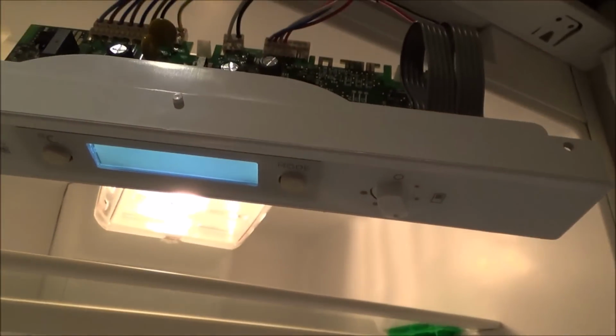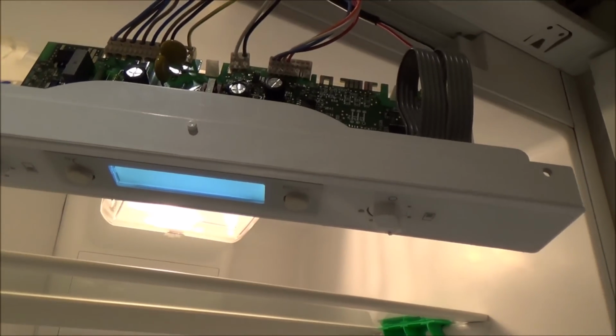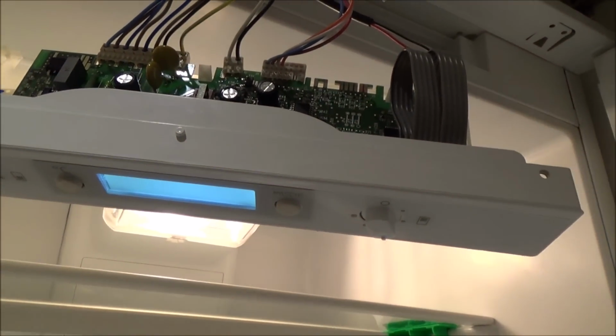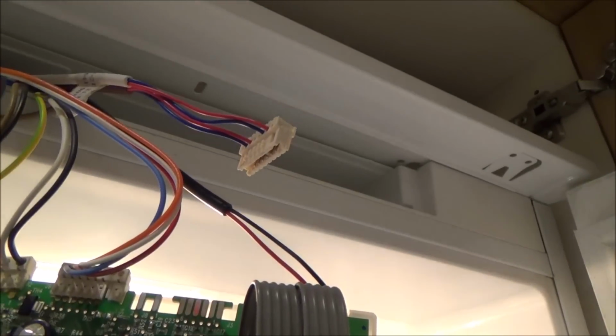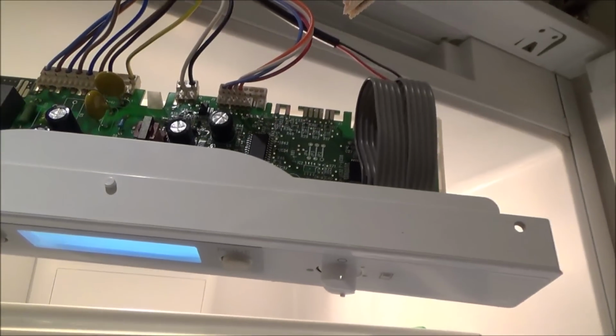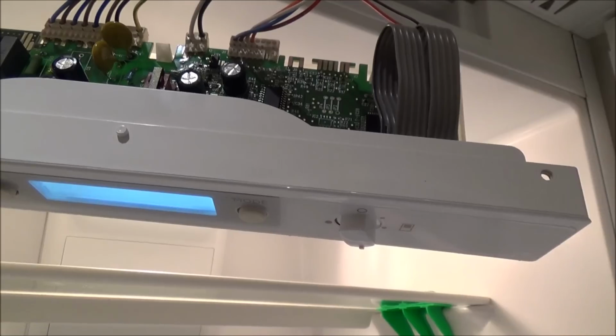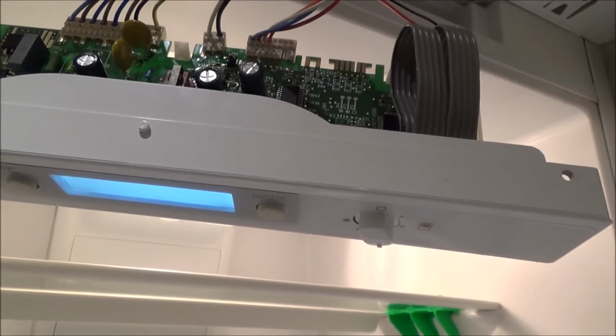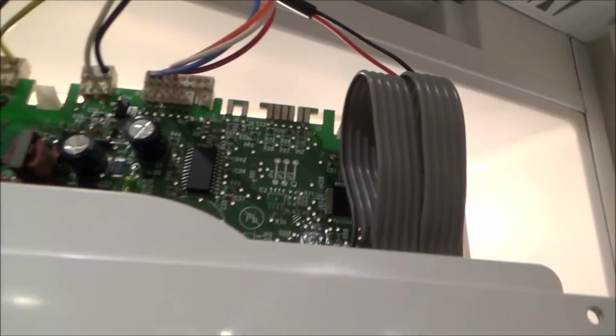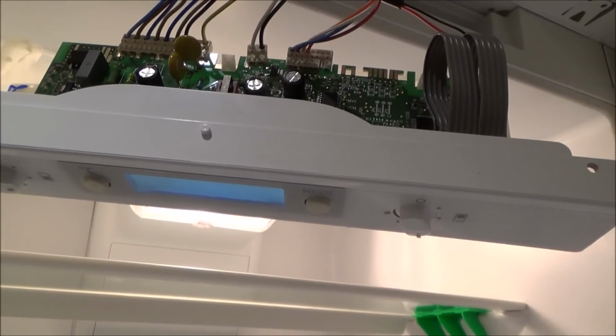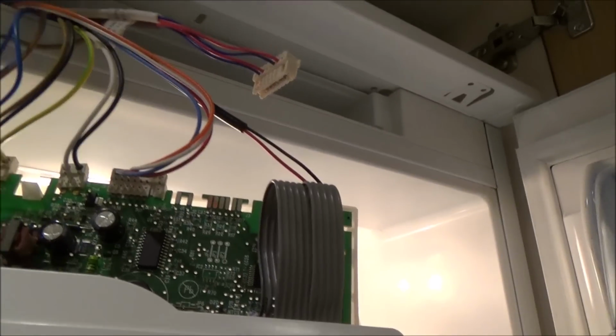So I'm wondering if that E1 fault is just a rogue fault, because if it's not the two sensors, and it's not those thermal switches which I know are working, then what else can it be? Maybe there's just something out of range, but maybe it's not actually a fault - maybe it's registering a fault even though there isn't one, because everything's testing okay.